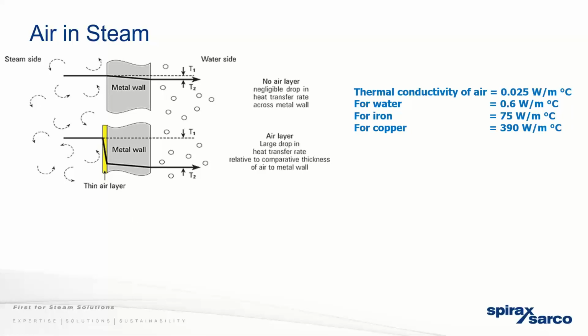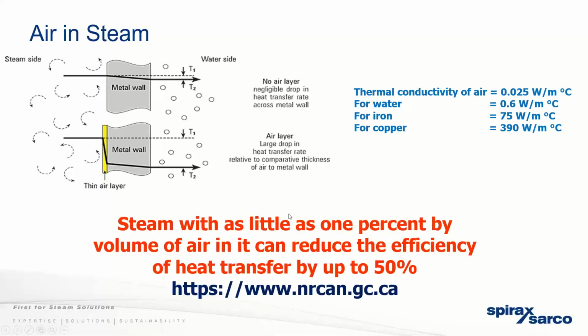Here's some numbers just showing the thermal conductivity of air. It is really low compared to water and to metals. And steam with as little as 1% by volume of air can reduce the efficiency of that heat transfer by up to 50%. So we know this is an inefficient way of heating. As you're bringing air in, it's going to reduce the efficiency of your heat exchanger. You're going to use more steam to achieve your heat transfer.